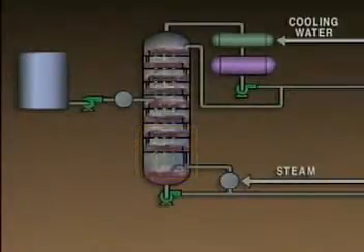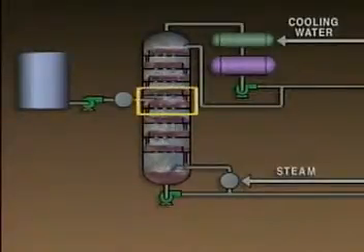move up the tower. Another place where temperature control is important is at the feed point. The temperature at the feed point should be within the boiling range of the mixture. The temperature at the feed point should be close to the temperature of the feed tray. The temperature of the feed tray depends on its physical location in the tower. For example, the lower the feed tray is in the tower, the higher its temperature will be.